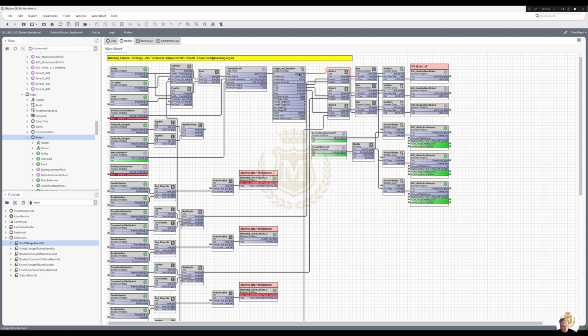Once we enable it, we will switch this PI loop in there, but we're using a numeric delay, and it's set at 0.50. So that is 0.5 every 1 second. So it will go up 0.5 every 1 second. So it stages up the boilers to 100%. And then when we turn the system off, we still have a 5 minute run time. So these start dropping down. Again, they drop down 0.5 every 1 second. So it won't take long to drop them down. These pumps will stay running for 5 minutes. And then once 5 minutes, so the heat exchanger will be cleared on the boilers, and then the pumps will then stop themselves.